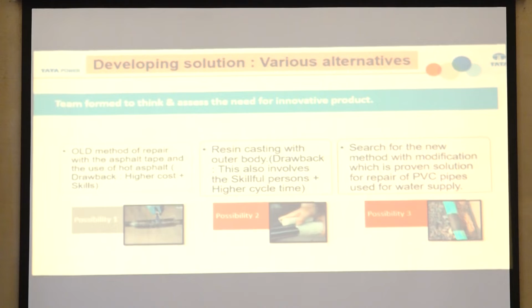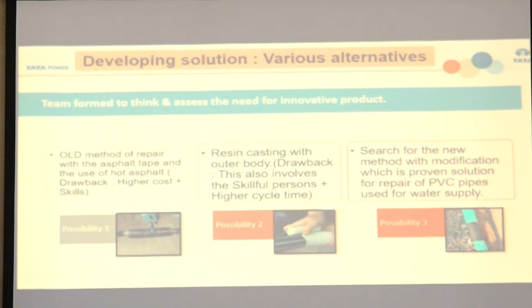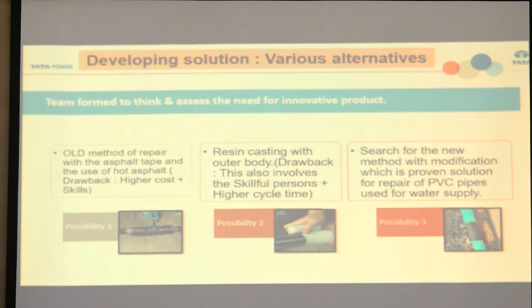The second is resin cast with an outer body. For this also you need a skilled person. Then we came across the third possibility. We did research and found many vendors or manufacturers who use a kit for repair of PVC pipes. But those are hard pipes, whereas cable outer PVC has other properties; it is soft. So we made some changes in that kit with 2-3 tubes. Then we tried it on our cables in the network, and after that we implemented it.